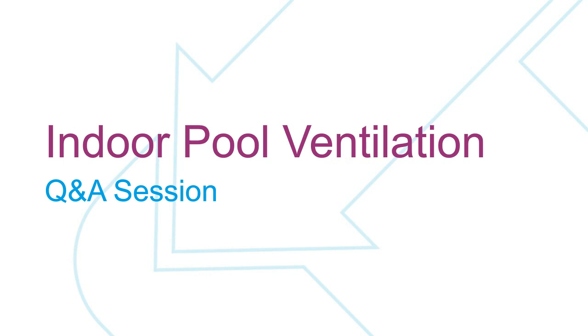Well, a lot of times you're trying to dehumidify at a point when the heat wheel would be humidifying. There's a theoretical argument that could say you might want to use it on the real coldest days in winter to avoid that low humidity thing I talked about. And you might be able to use them on days when the outside air is more humid than this pool space. But remember, the pool space is 85 and 70 degree dew point or something like that, so there aren't many hours. And then you get into the issues of swimming pools, of heat wheels, and how reliable they're going to be in that corrosive atmosphere. So far, we've really mainly replaced them, frankly.